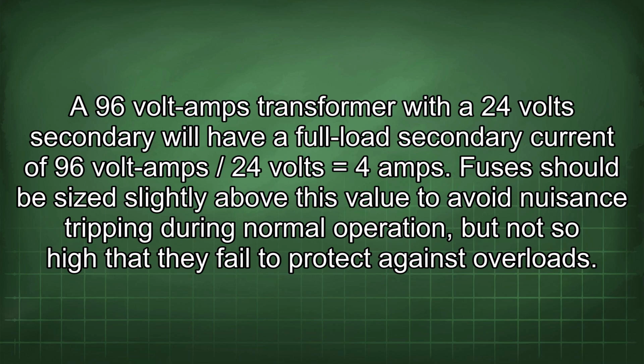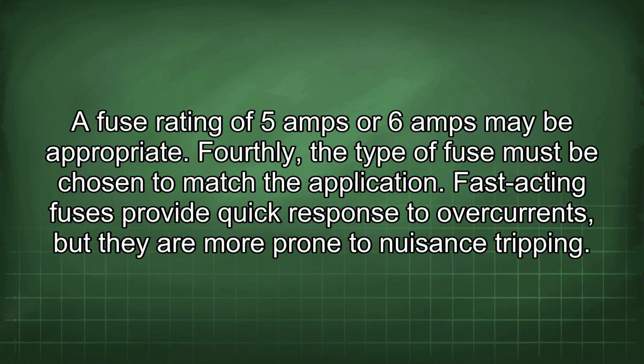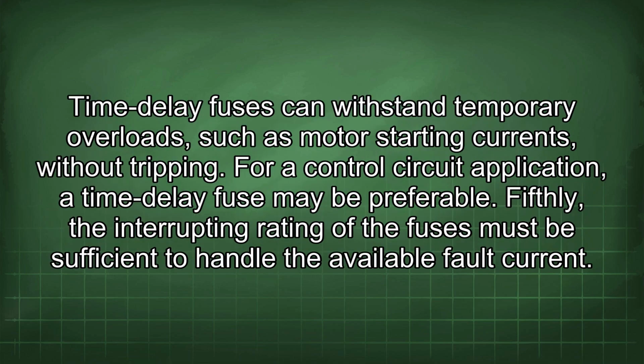Fuses should be sized slightly above this value to avoid nuisance tripping during normal operation, but not so high that they fail to protect against overloads. A fuse rating of 5 amps or 6 amps may be appropriate. Fourthly, the type of fuse must be chosen to match the application. Fast-acting fuses provide quick response to overcurrents, but they are more prone to nuisance tripping. Time delay fuses can withstand temporary overloads, such as motor starting currents, without tripping. For a control circuit application, a time delay fuse may be preferable.